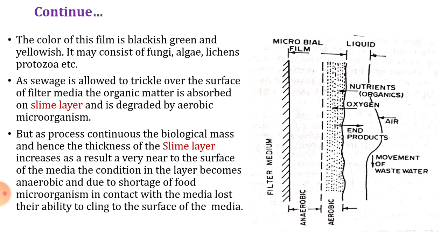So if you refer to the figure, when the wastewater, which is shown by the liquid zone, trickles over and comes in contact with the aerobic layer biofilm, the microorganisms present in the biofilm take up the nutrients and oxygen from it, stabilize the organic matter, release the end products and carry out the decomposition. But as the process continues, the biological mass and hence the thickness of slime layer increases.